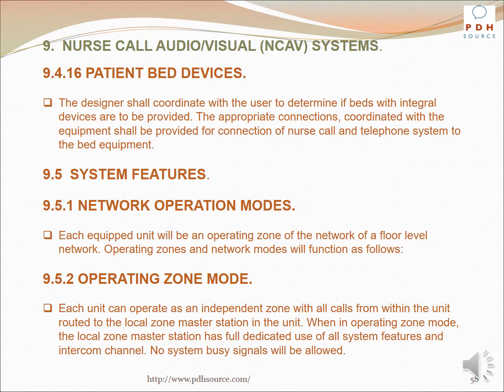The designer shall coordinate with the user to determine if beds with integral devices are to be provided. The appropriate connections coordinated with the equipment shall be provided for connection of nurse call and telephone system to the bed equipment. Each equipped unit will be an operating zone of the network of a floor-level network. Operating zones and network modes will function as follows.